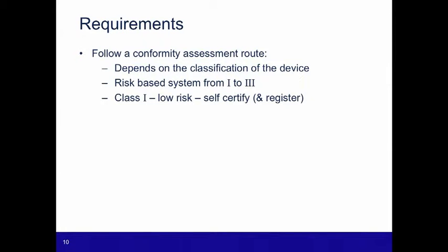So the requirements for medical devices are that you must follow a conformity assessment. And this depends on the classification of the device. So classification is a risk-based system from class 1, which is the lowest risk, to class 3.